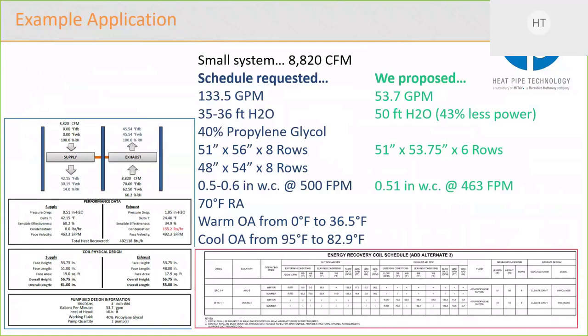Now, what I will draw your attention to is, it's hard to see on the left, so if you can't read it, I apologize. You're going to have to trust me on that one. We're actually showing a bigger pressure drop on the exhaust coil. We're showing 1.05 inches. But we're also showing condensation, and this is where our selection process can be very valuable. So in this application, we knew that in winter there was going to be condensation across the exhaust coil. And that condensation on the fins causes a greater pressure drop.